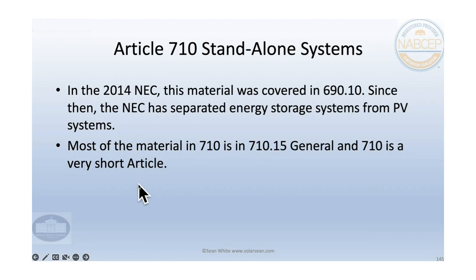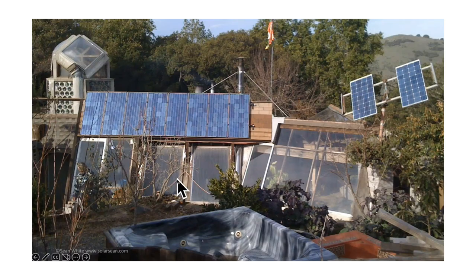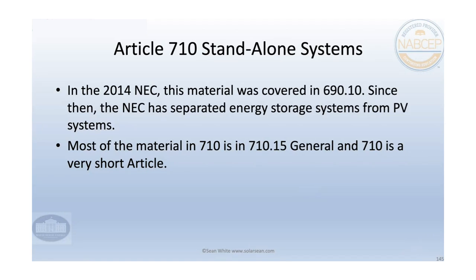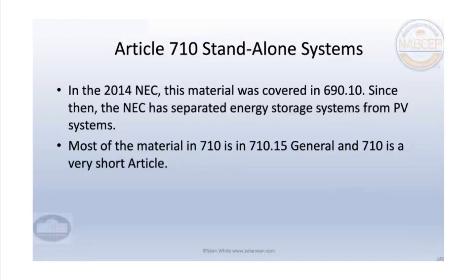So standalone systems also was moved into its own article away from Article 690. And so there's a little bit about that. There was a couple questions posted in the chat, and I know you can't see the chat. Do you mind if we just look at those real quick, or maybe I can state them? So one of the inspectors, Richard, asked, is an ESS required for a residential solar and battery PV system? And then there was a response. There are requirements for PV to have exterior disconnect, rapid shutdown. There are also requirements for ESS to have an exterior disconnect. And then there's a question associated with it. Does code require these to be the same disconnect switch, or can they be separate?